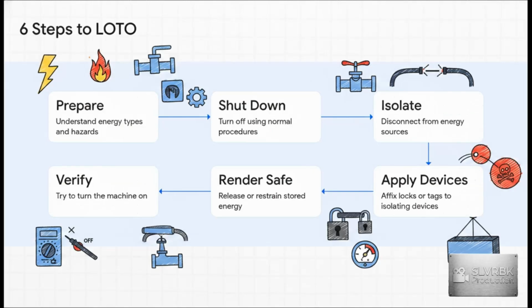Now, before beginning service, you must complete 6 steps in exact sequence. 1. Prepare for shutdown. 2. Shut down the machine. 3. Disconnect or isolate the machine from its energy source. 4. Apply the lockout or tagout device. 5. Render safe all potential hazardous stored energy. And 6. Verify the isolation and de-energization of the machine. Skipping even one of these steps, especially that final verification step, can be fatal.